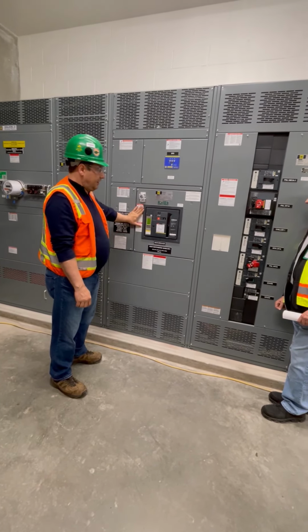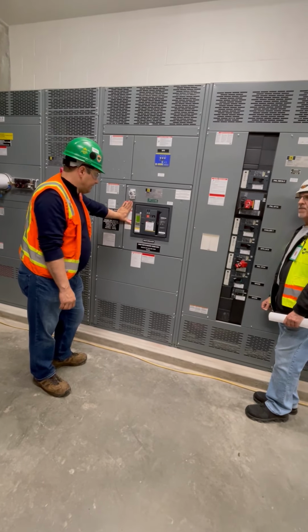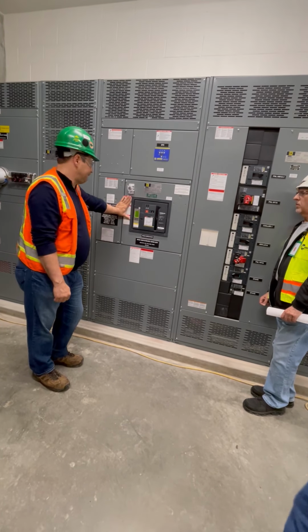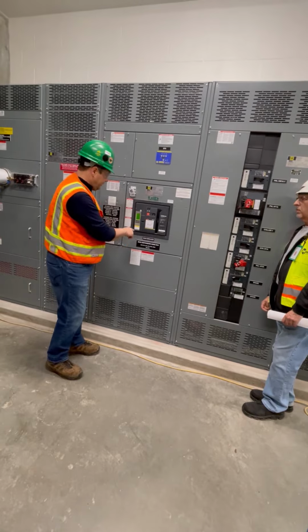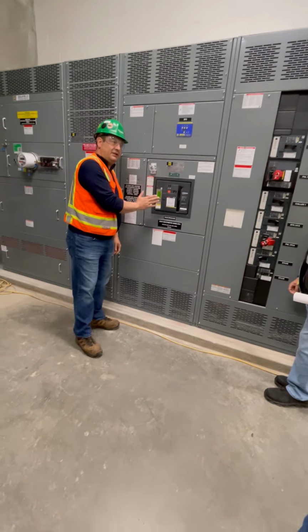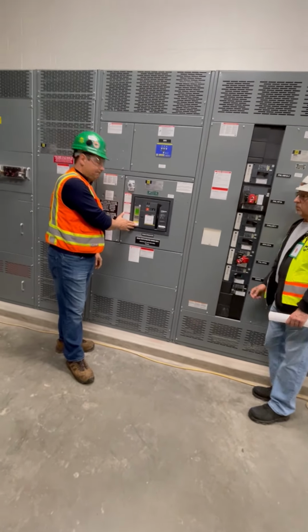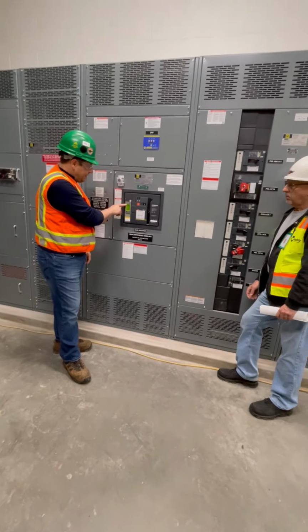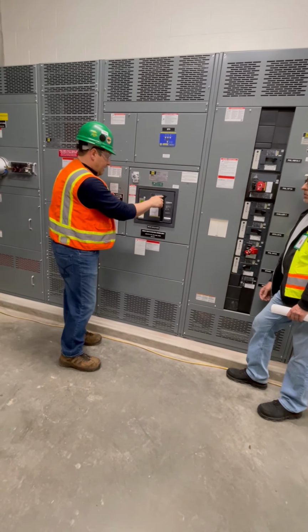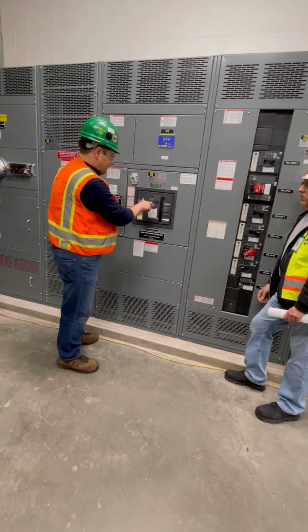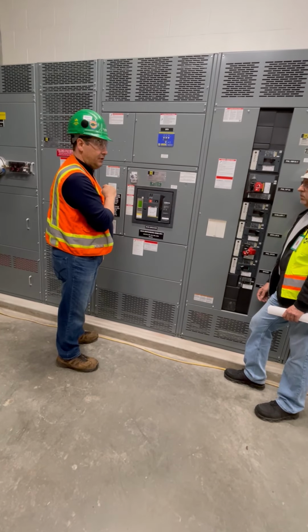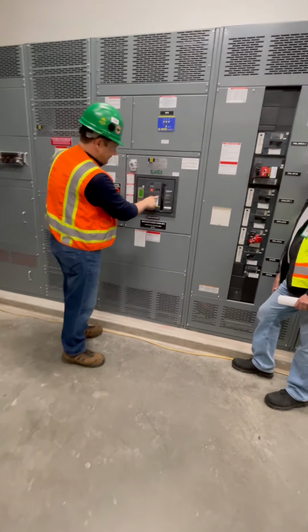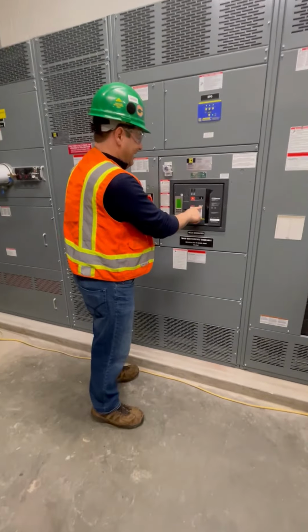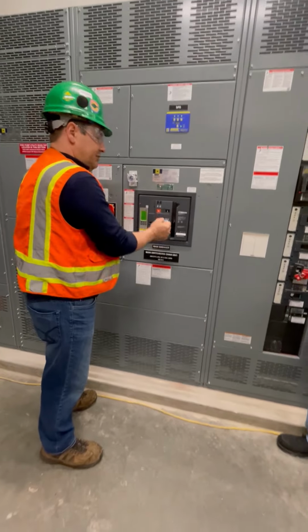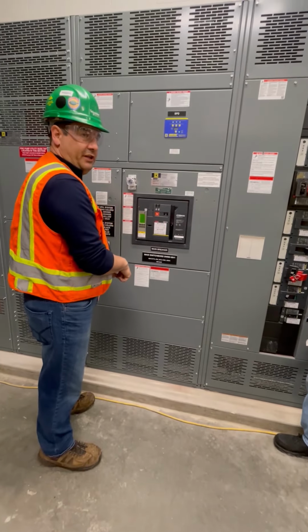On the breakers, these breakers are NW breakers. To operate this breaker, here are the settings. Assuming it's all set, you don't have to touch this. You have a couple of LEDs up here, but in order to operate the breaker, you have to pull this. So you have the open close button, okay? If the breaker's in, and then you have the charged flag. What you have to do is crank this up until this is charged, and then you can close the breaker.